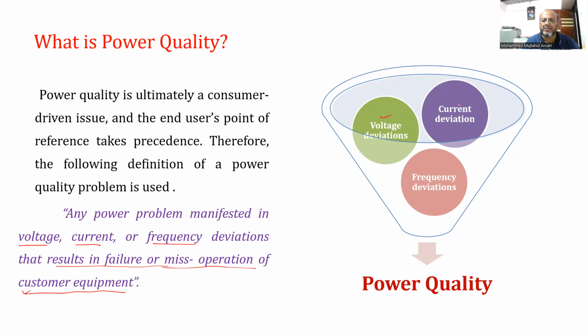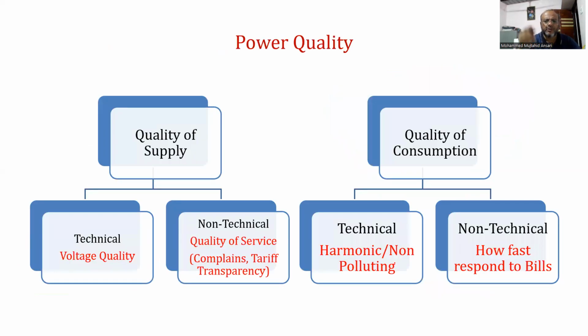Any deviation, it may be a voltage deviation, a current deviation, or a frequency deviation, in one of the quantities or any two of the quantities, will give a power quality issue. So we have the quality of supply and the quality of consumption. The quality of supply is the voltage quality. One part is technical and the second is non-technical. In the technical part, the voltage should be sinusoidal and constant throughout the operation time, the waveform should be constant, and there should not be any deviation in the maximum voltage and average voltage. The voltage magnitude is constant, and the voltage is balanced in all three phases. These are the voltage quality, and that is the technical one.